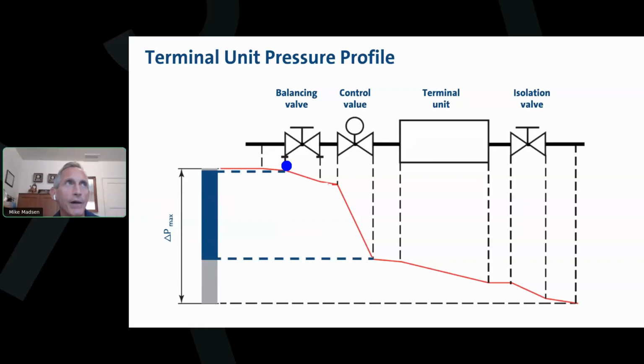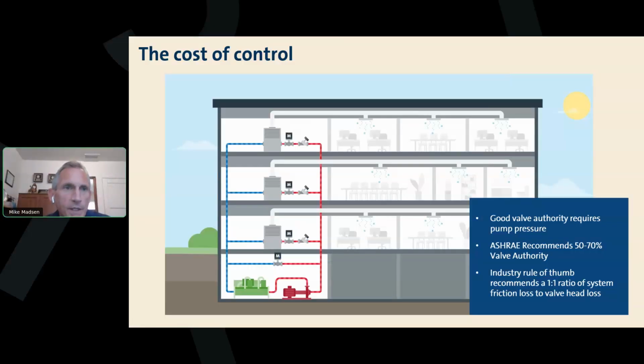how much control that valve is able to exert on the flow. And so if you have very low valve authority, you're not getting any control. You'll have low valve authority if you have an oversized valve. An oversized valve isn't going to give you any control. It's going to basically be an on-off valve. The opposite side of the spectrum is if you have a very high valve authority, you're going to get perfect flow control, but it's going to come at a huge cost. You're going to have a big pressure drop to get that flow control. So what's the cost of valve authority? What's the cost of that control? ASHRAE recommends that you use a valve authority of 50 to 70%.